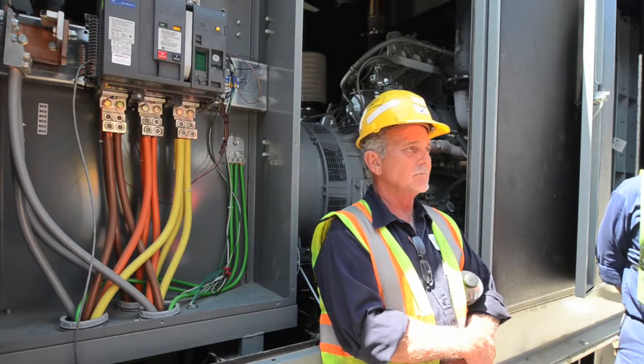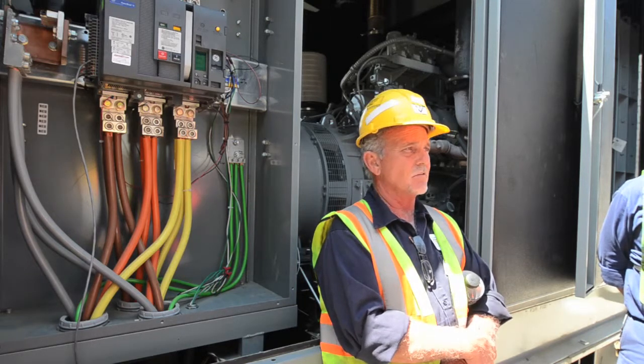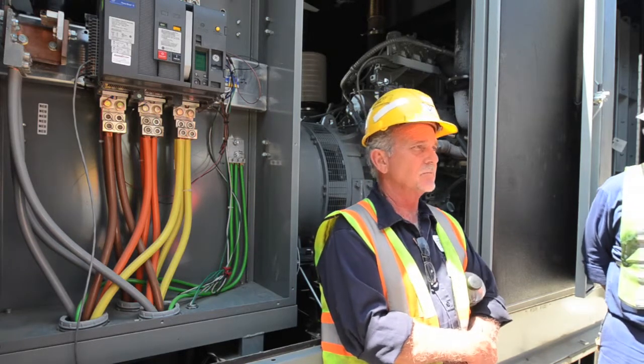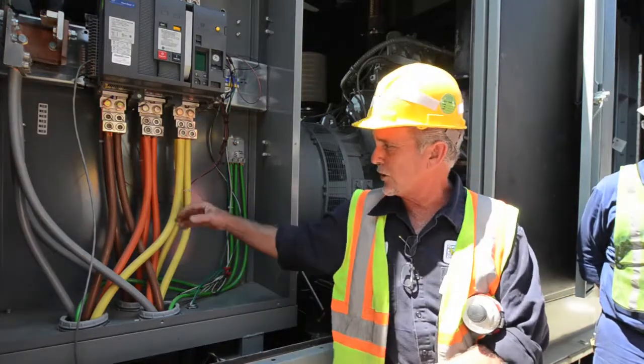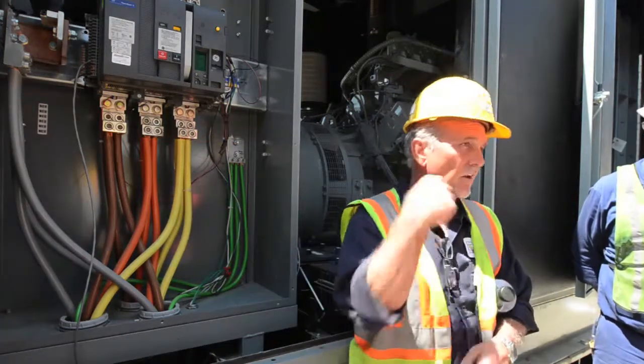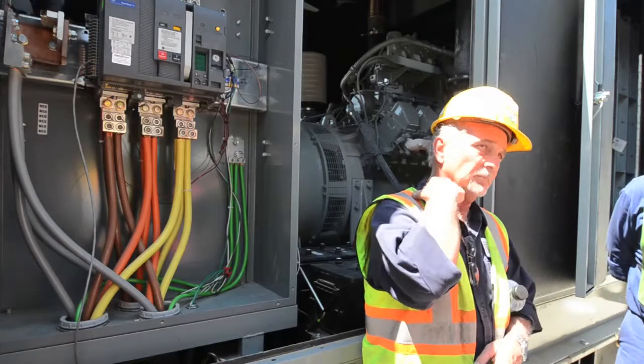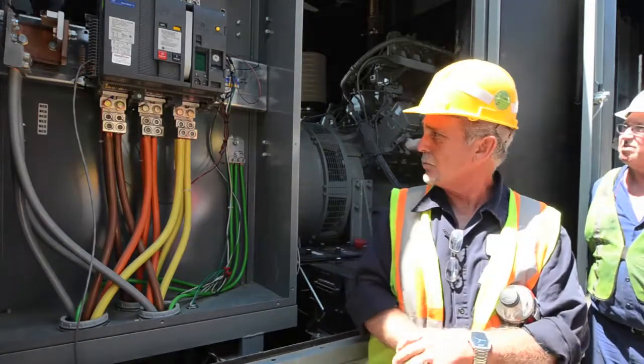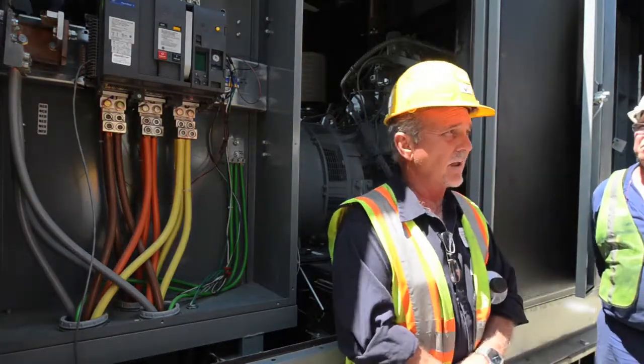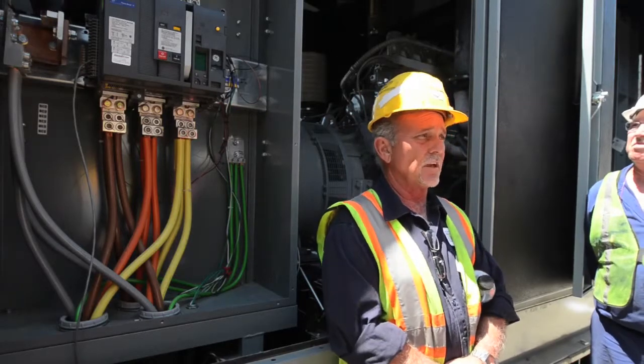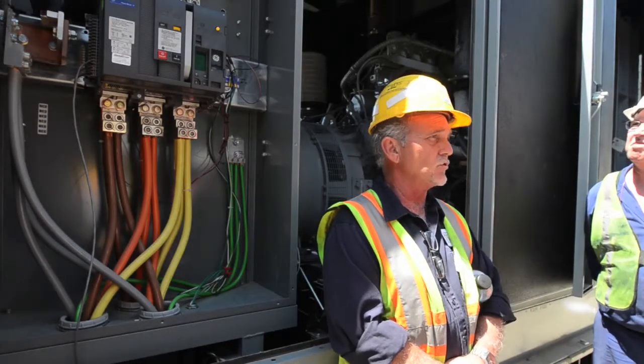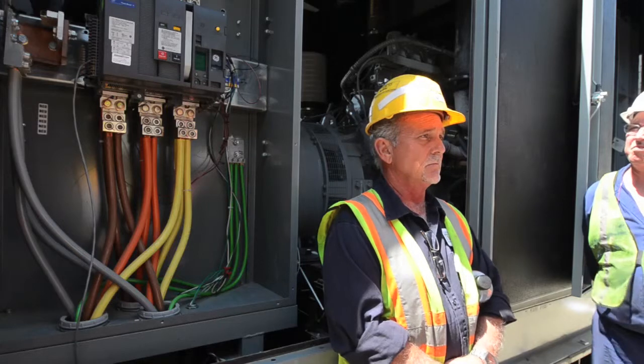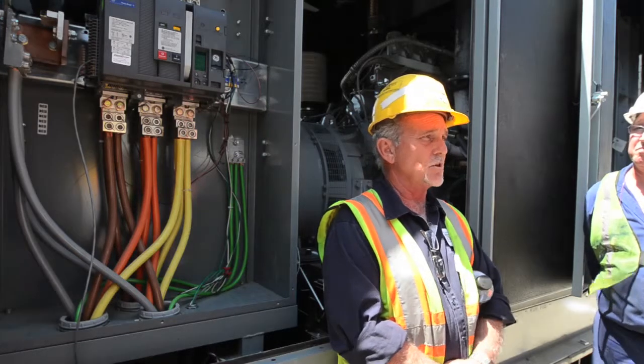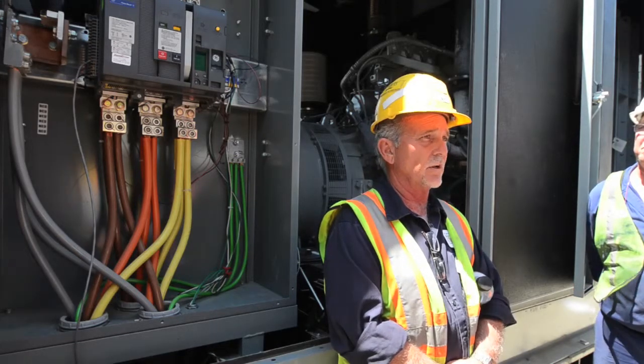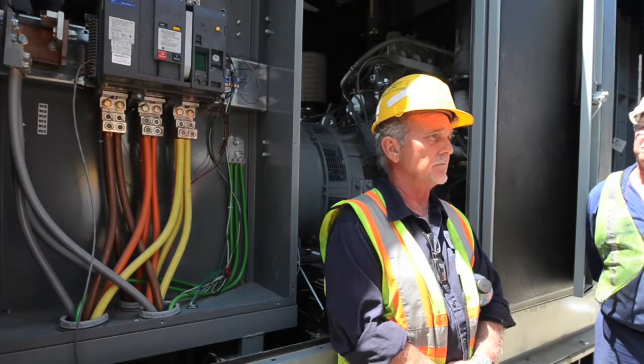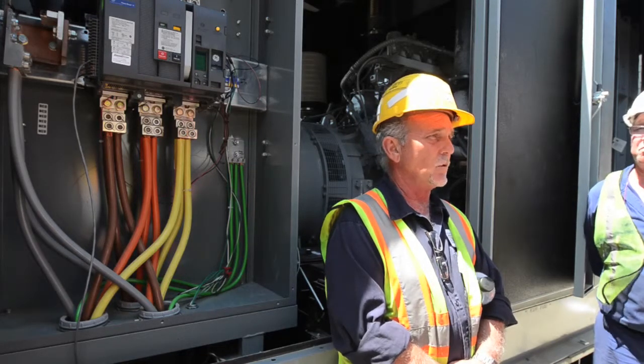It gets real ugly. So that's why you'd always want to back it up with another 650, and you want to make your ties right here. And like I said, these can be pulled off. They can tie right onto these and send it on its way. So, like I said, when it calls out these generators, remember it's going to call out both of them. Every single time you have an outage, both of them are coming up, and then it will shed the one that it doesn't need. And then in the event that you start drawing too much power, it'll automatically start the other one. It'll synchronize and it'll go online and share it. So it'll be quite the automated system.